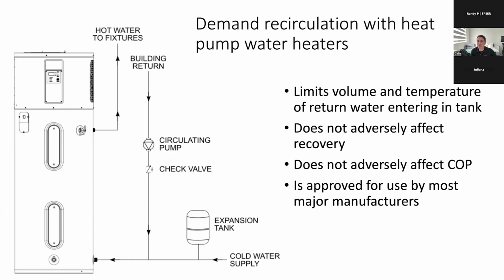But I think a lot of builders are also taking the initiative to do more of their projects using heat pump water heaters. But the thing about heat pump water heaters is that if the pump is running excessively, you lose all the efficiency and you lose heating capacity. So all the major manufacturers now, from A.O. Smith to Rheem to Bradford, are saying that you need to use some type of on-demand system that meets the energy code requirements. That way you can preserve your efficiency. It'll stay in heat pump mode, it won't be kicking on these heating elements, and you won't be running out of hot water. So that's the benefit of marrying an on-demand system with a heat pump water heater.